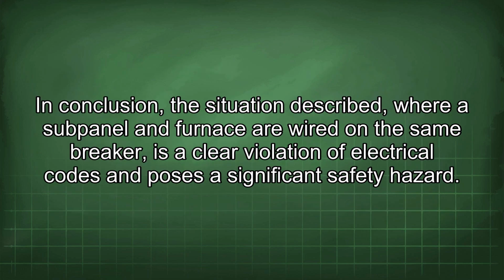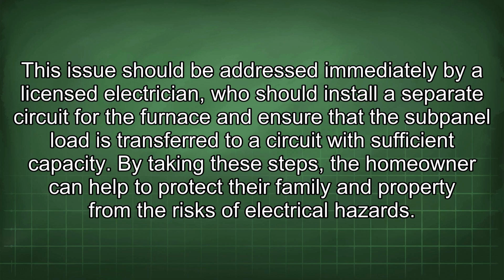In conclusion, the situation described, where a subpanel and furnace are wired on the same breaker, is a clear violation of electrical codes and poses a significant safety hazard. This issue should be addressed immediately by a licensed electrician who should install a separate circuit for the furnace and ensure that the subpanel load is transferred to a circuit with sufficient capacity. By taking these steps, the homeowner can help to protect their family and property from the risks of electrical hazards.